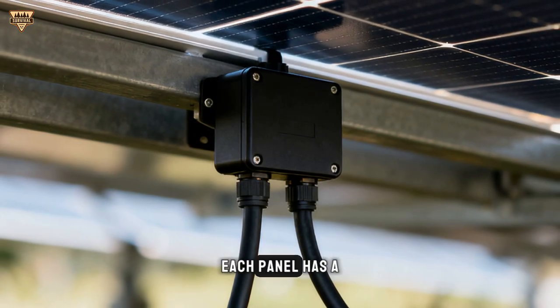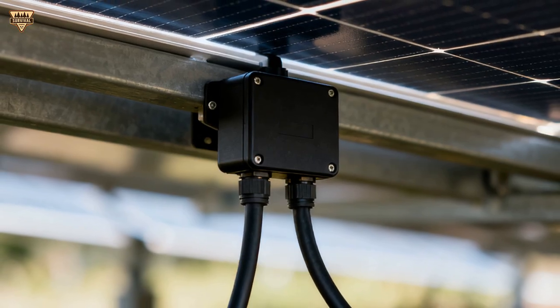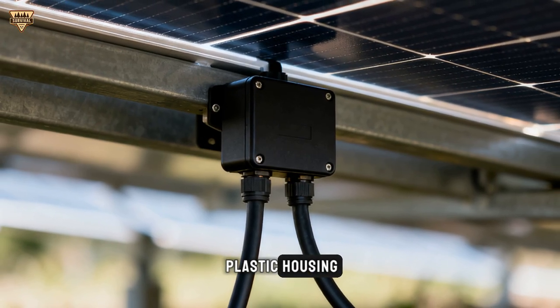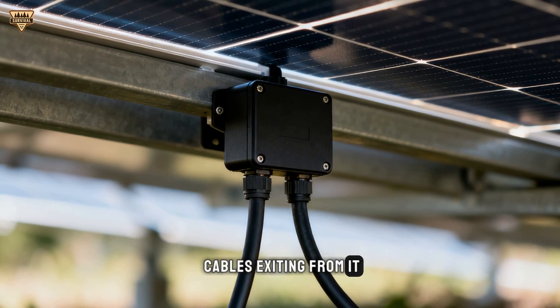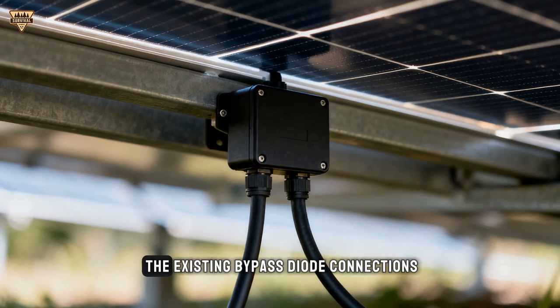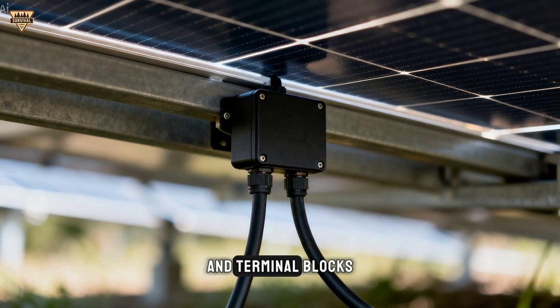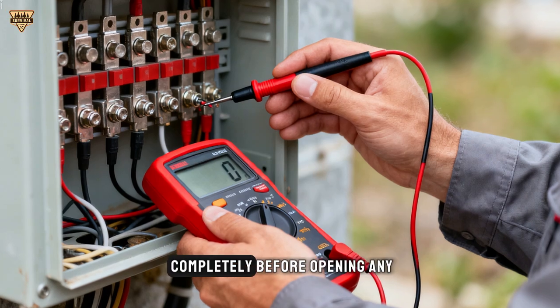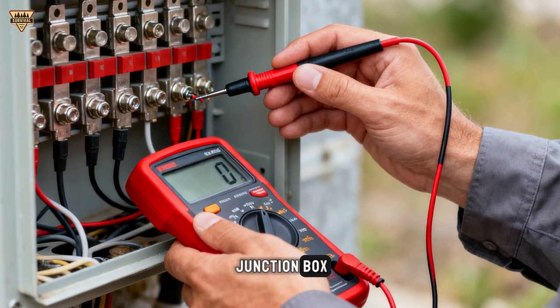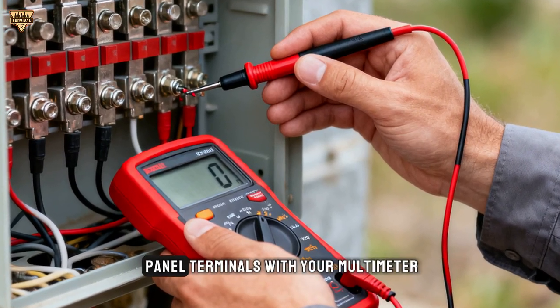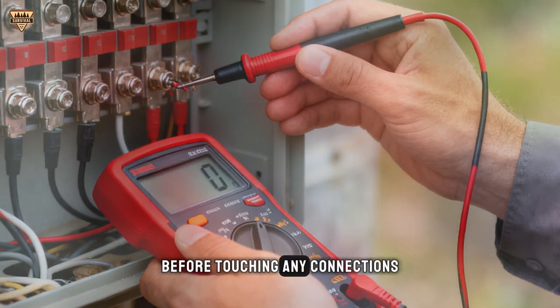Step 2. Access junction boxes. Each panel has a junction box on its rear surface, typically a small weatherproof plastic housing with the DC output cables exiting from it. The junction box contains the existing bypass diode connections and terminal blocks. Power down your system completely before opening any junction box. Confirm 0 voltage across panel terminals with your multimeter before touching any connections.